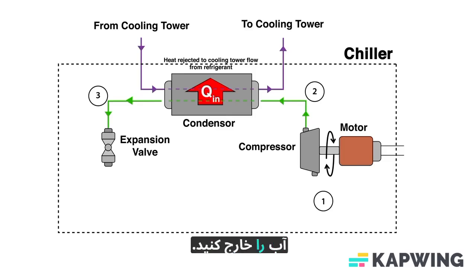The different types of condensers will be discussed in a bit, but for now it is important to know that the refrigerant leaves the condenser at a cooler temperature. At this point, the refrigerant is ready to be depressurized and used to absorb heat from a building. Once the refrigerant leaves the condenser, it reaches the expansion valve. This valve depressurizes the refrigerant, much like covering the end of a garden hose with your thumb and letting out a fine mist of water.